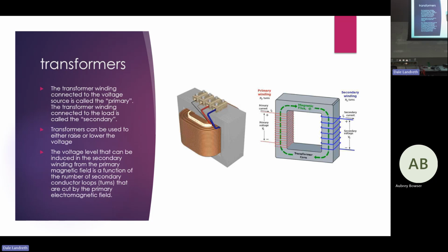Transformers can be used to either raise or lower the voltage. Is there a difference between a step up and step down transformer as far as how it's built? Yes, there is. 100%. So the difference is if you backfeed one—if you're using it to drop the voltage, all your current is going to hit on the low voltage side. If you reverse feed it, they increase the winding size on the opposite side of the transformer, so the secondary side can now take the inrush current.